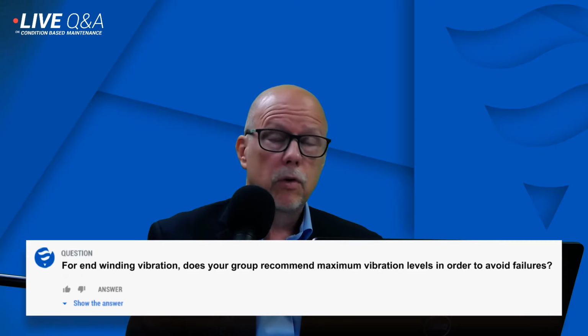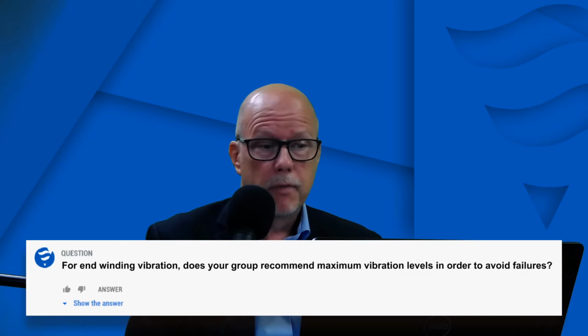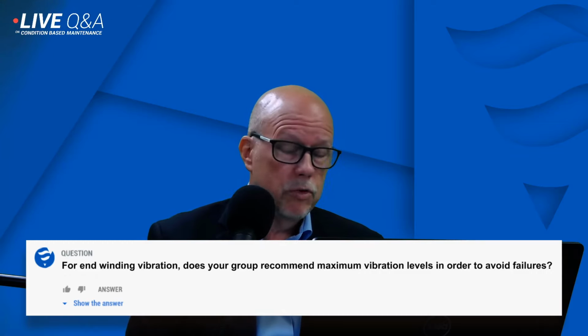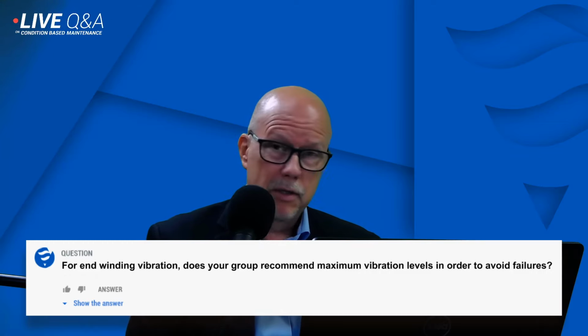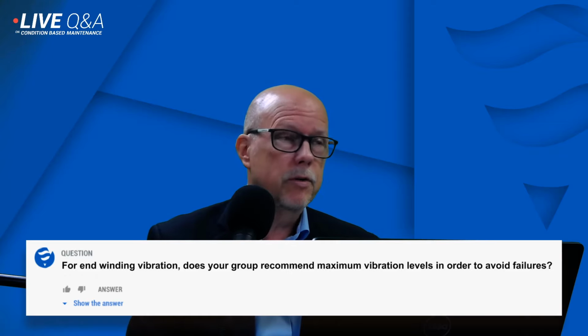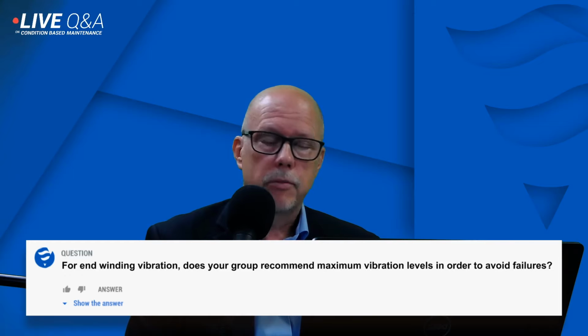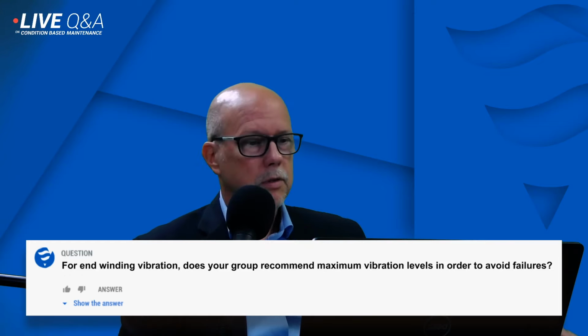So there are no international standards, but we've been monitoring end winding vibration on turbo generators, on sag mills, ball mills, on hydro generators for over 25 years. And we have our own values that we use to assess the severity, and quite a few customers use those same tolerances.